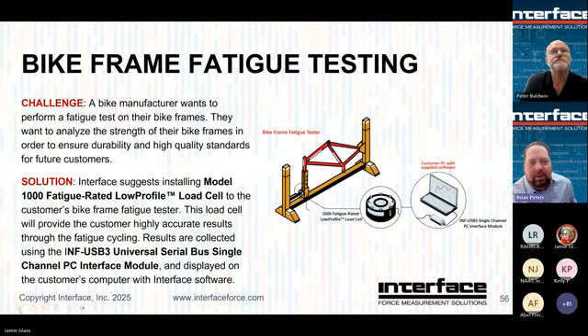All right. Example of a basic component fatigue test setup. So using our 1000 series fatigue rated low profile, doing push-pull testing on a component. In this case, packaged with our INF USB. Nice thing about it is it comes with software. It comes with start-stop triggers, just like we talked about earlier. So it's real versatile software included with the instrument. Allows you to have pretty much a turnkey data acquisition testing solution ready to go. So again, doing fatigue testing, need push-pull, 1000 series, always the best bet.